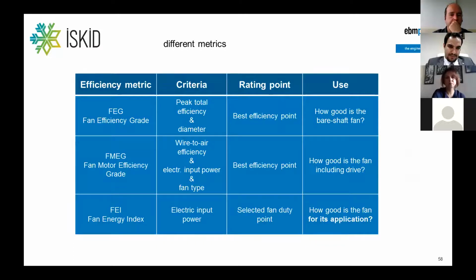So if we compare the FEG, the FMEG, and the Fan Efficiency Index, what is rated is the best efficiency point, and the fan selected duty point. And what does it help for? FEG evaluates the fan, the bare shaft fan. FMEG looks into how good the fan is, including the motor. And the FEI looks into how good the fan is for its application.